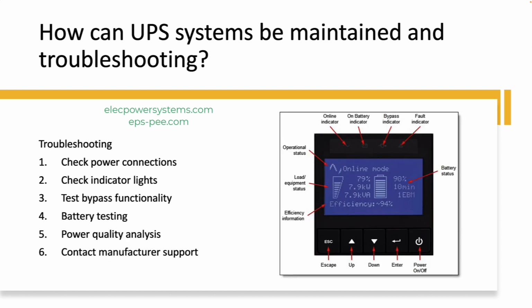Troubleshooting. Check power connections. Verify that the UPS system is properly connected to the main power supply and the devices and equipment it is protecting. Ensure all power cables and connectors are securely plugged in. Check indicator lights. Check the UPS system's indicator lights or display panel for any error codes, warnings, or alarms. Consult the user manual or manufacturer's documentation to interpret the indicators and take appropriate action. Test bypass functionality. If the UPS system has a bypass circuit, test its functionality by switching the UPS to bypass mode and checking if the connected devices receive power directly from the utility.